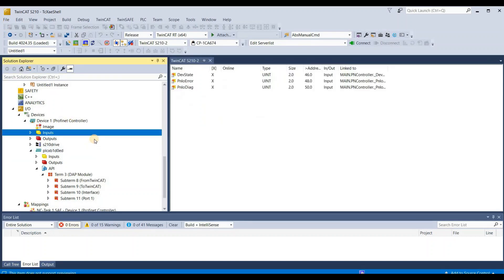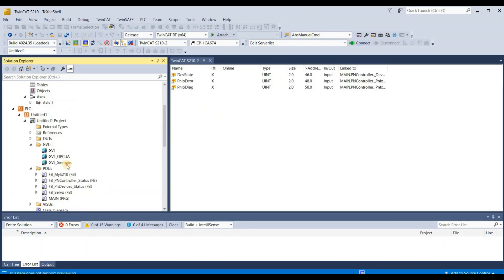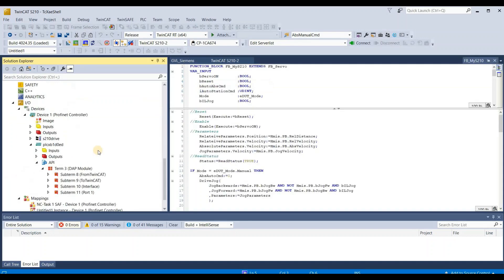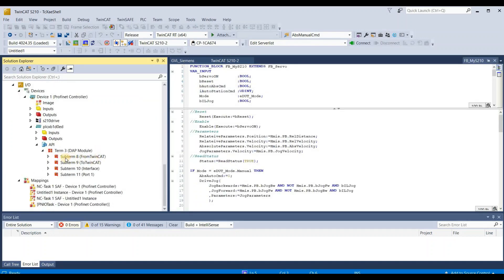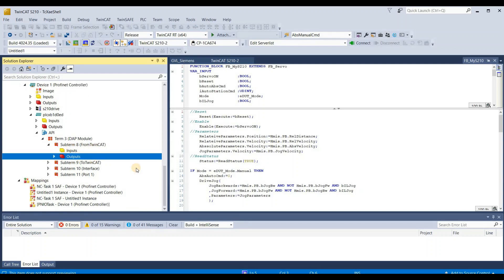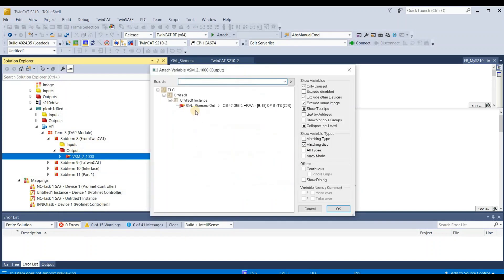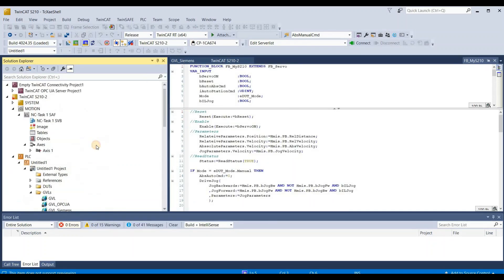Save it. Then we can map the data. I've already created a GVL_Siemens variable here with input and output process images of 20 bytes. Go to subitem 'From TwinCAT', select the output, select this item, right-click, change name, and then link the process image. Do the same for input. Right-click, done. Data is mapped.